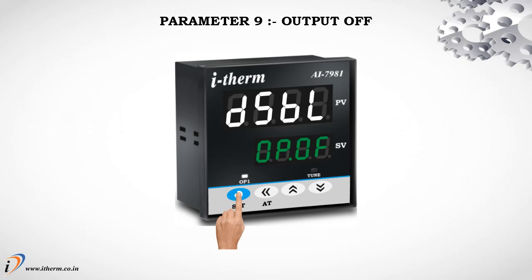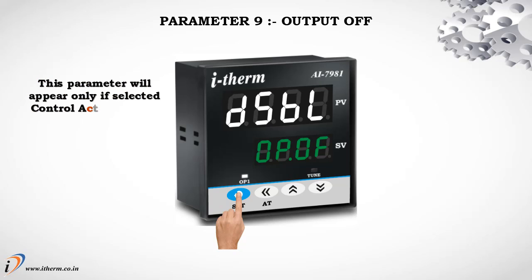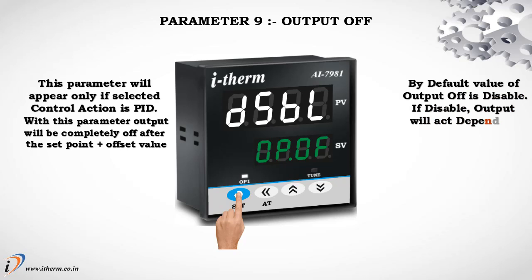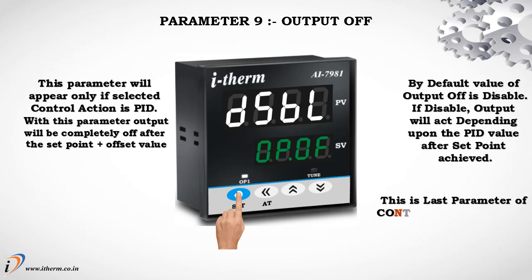Parameter 9: Output Off. This parameter will appear only if selected control action is PID. With this parameter, output will be completely off after the set point plus offset value. By default, value of output off is disabled. If disabled, output will act depending upon the PID value after set point is achieved. This is the last parameter of control list. Press set key to enter in run mode.